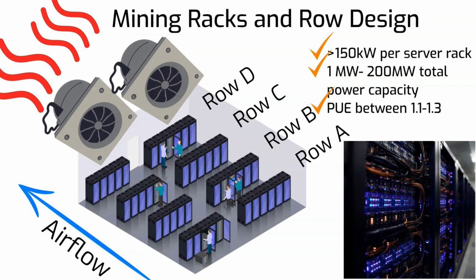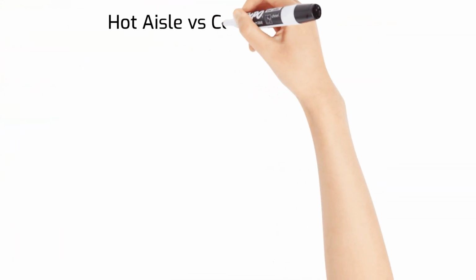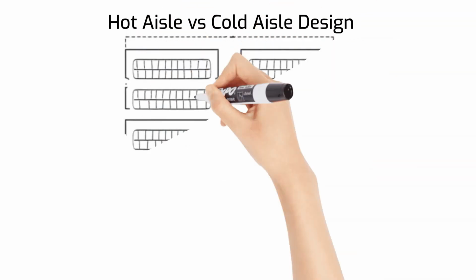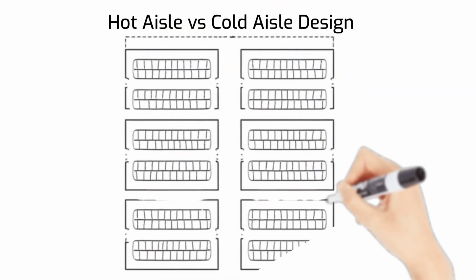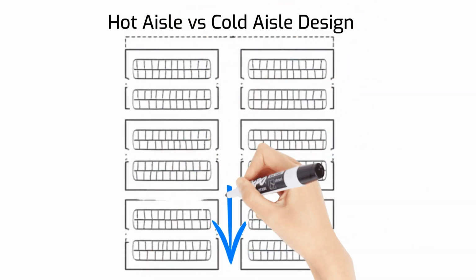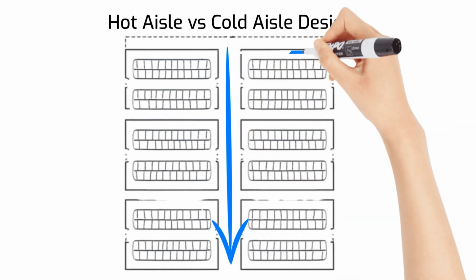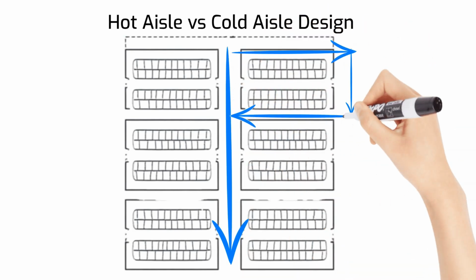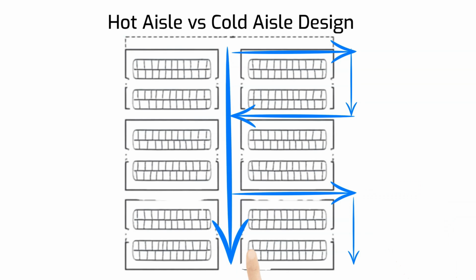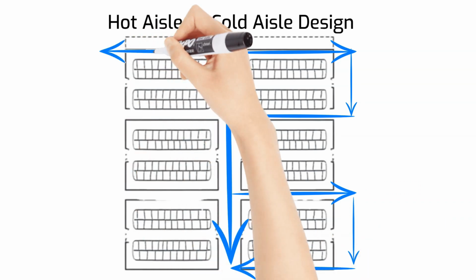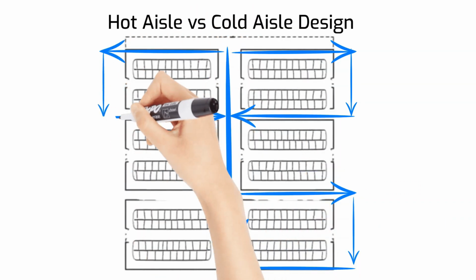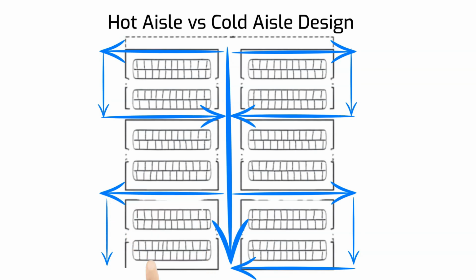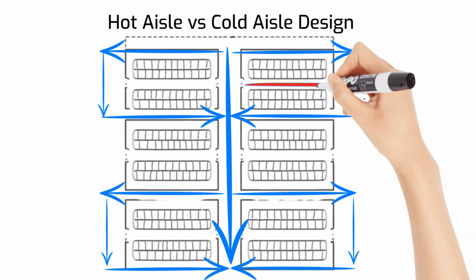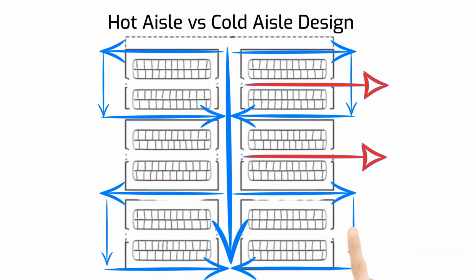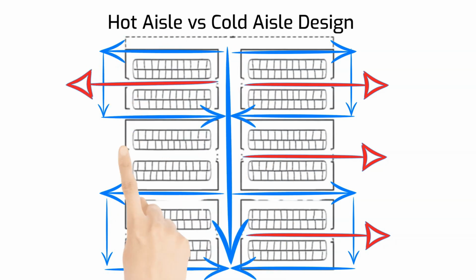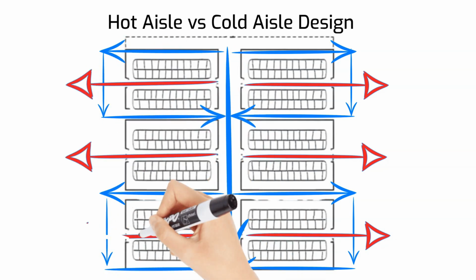One of the most common layouts is the hot aisle, cold aisle design. Cold air is delivered into specific aisles, while hot air is pushed out through separate paths. Keeping these airstreams separated prevents machines from recycling their own heat. This simple layout decision can dramatically improve efficiency and extend hardware lifespan. This separation is crucial for cooling efficiency, with physical barriers, like insulation panels or containment systems, used to prevent the mixing of hot and cold air.